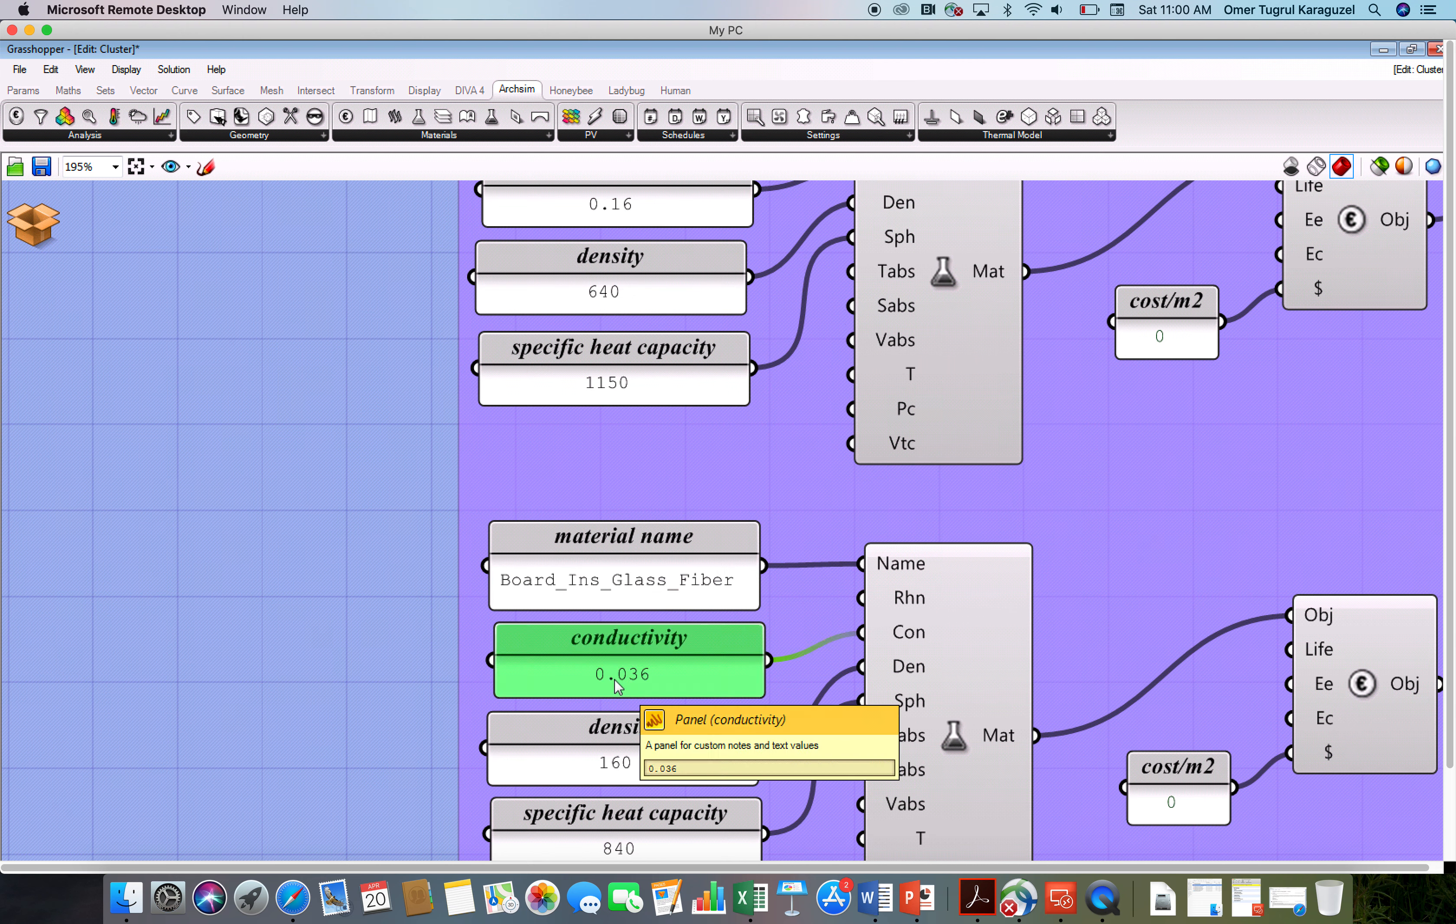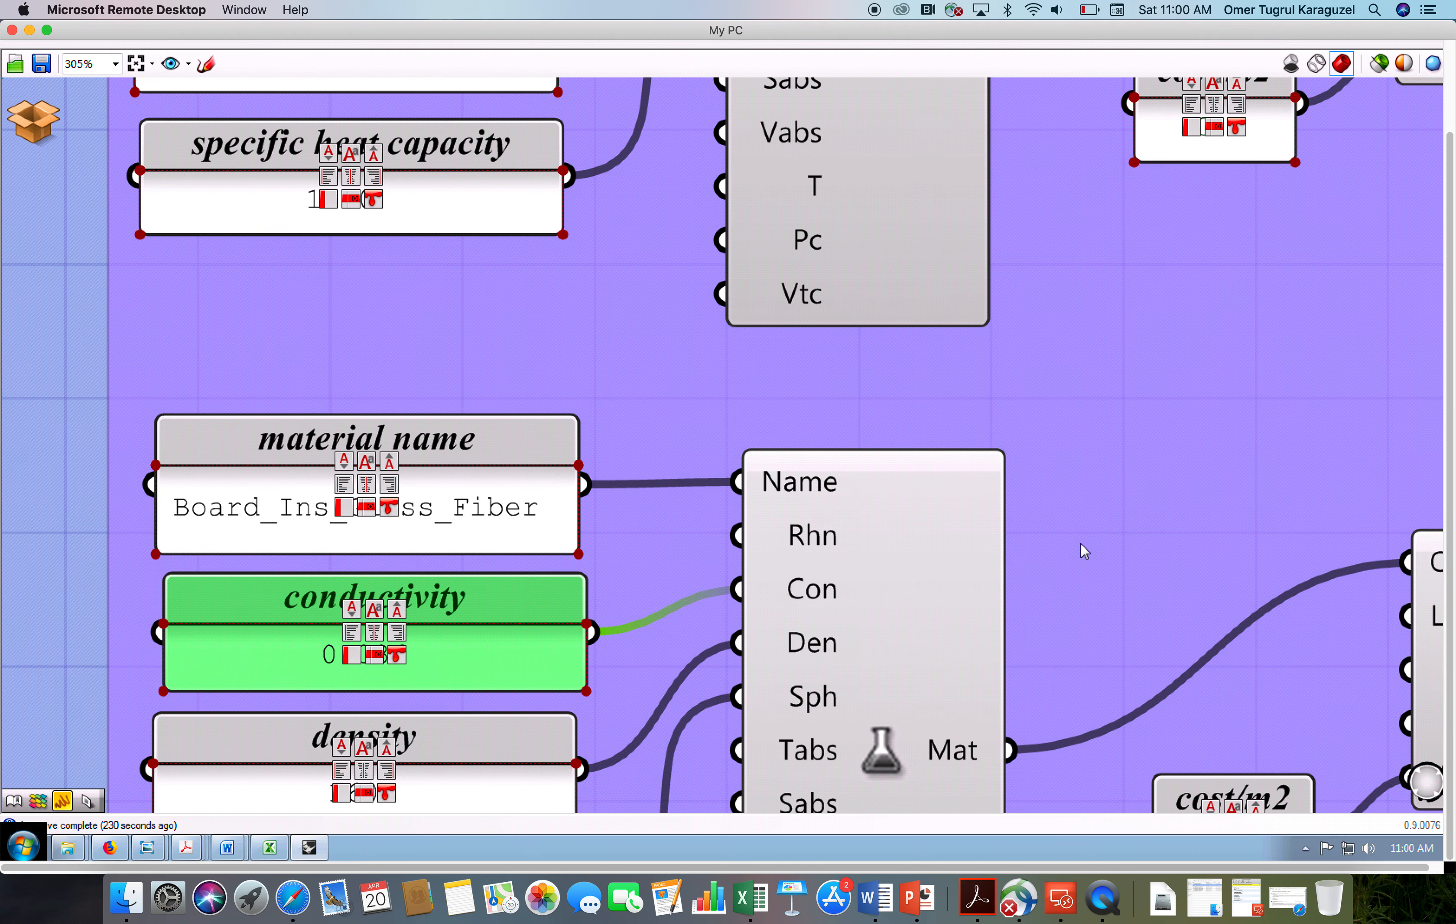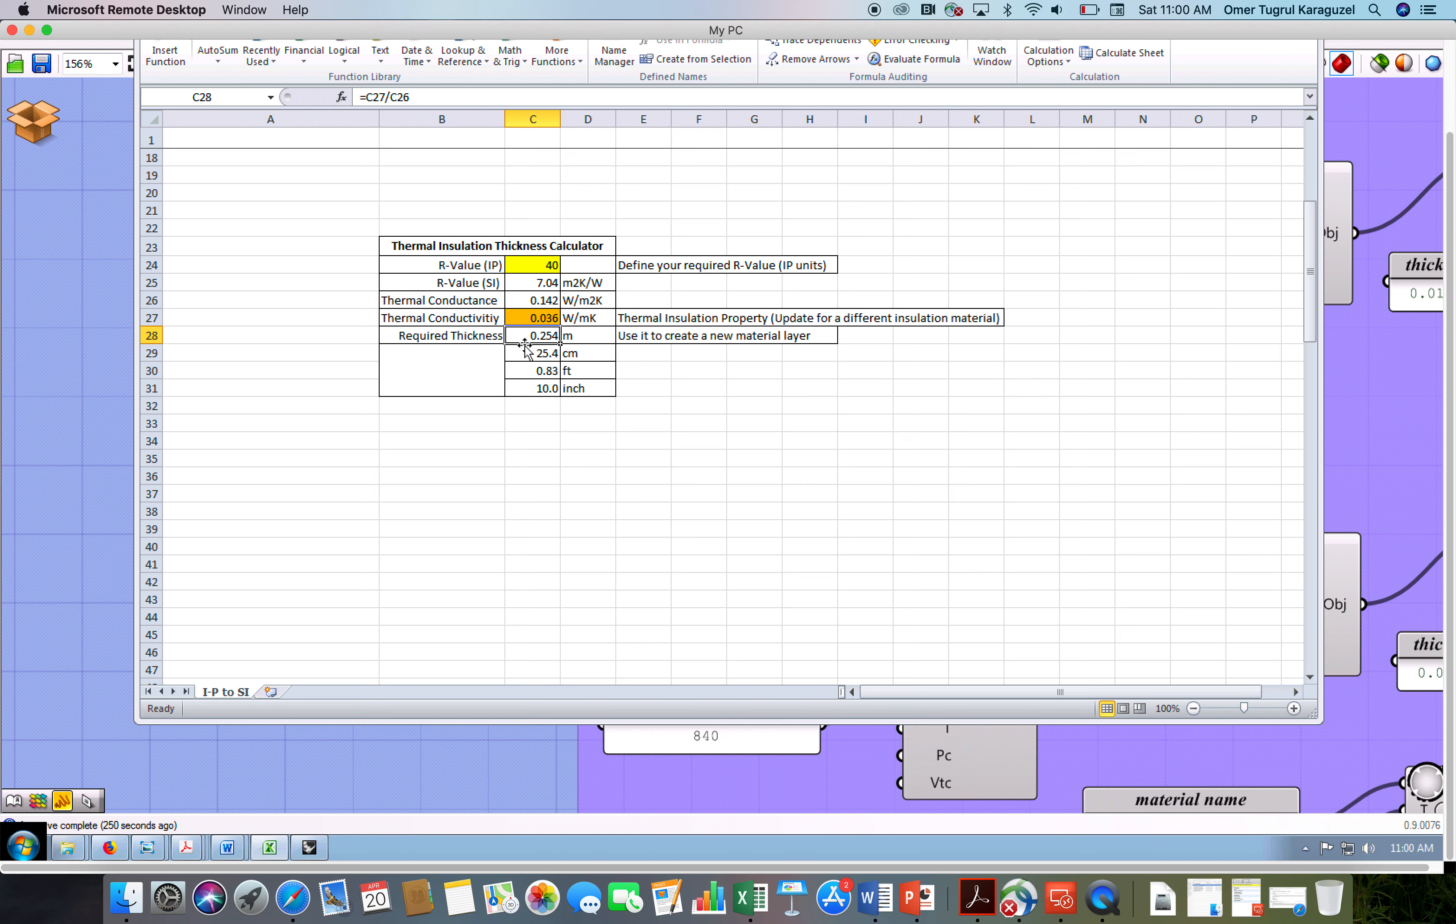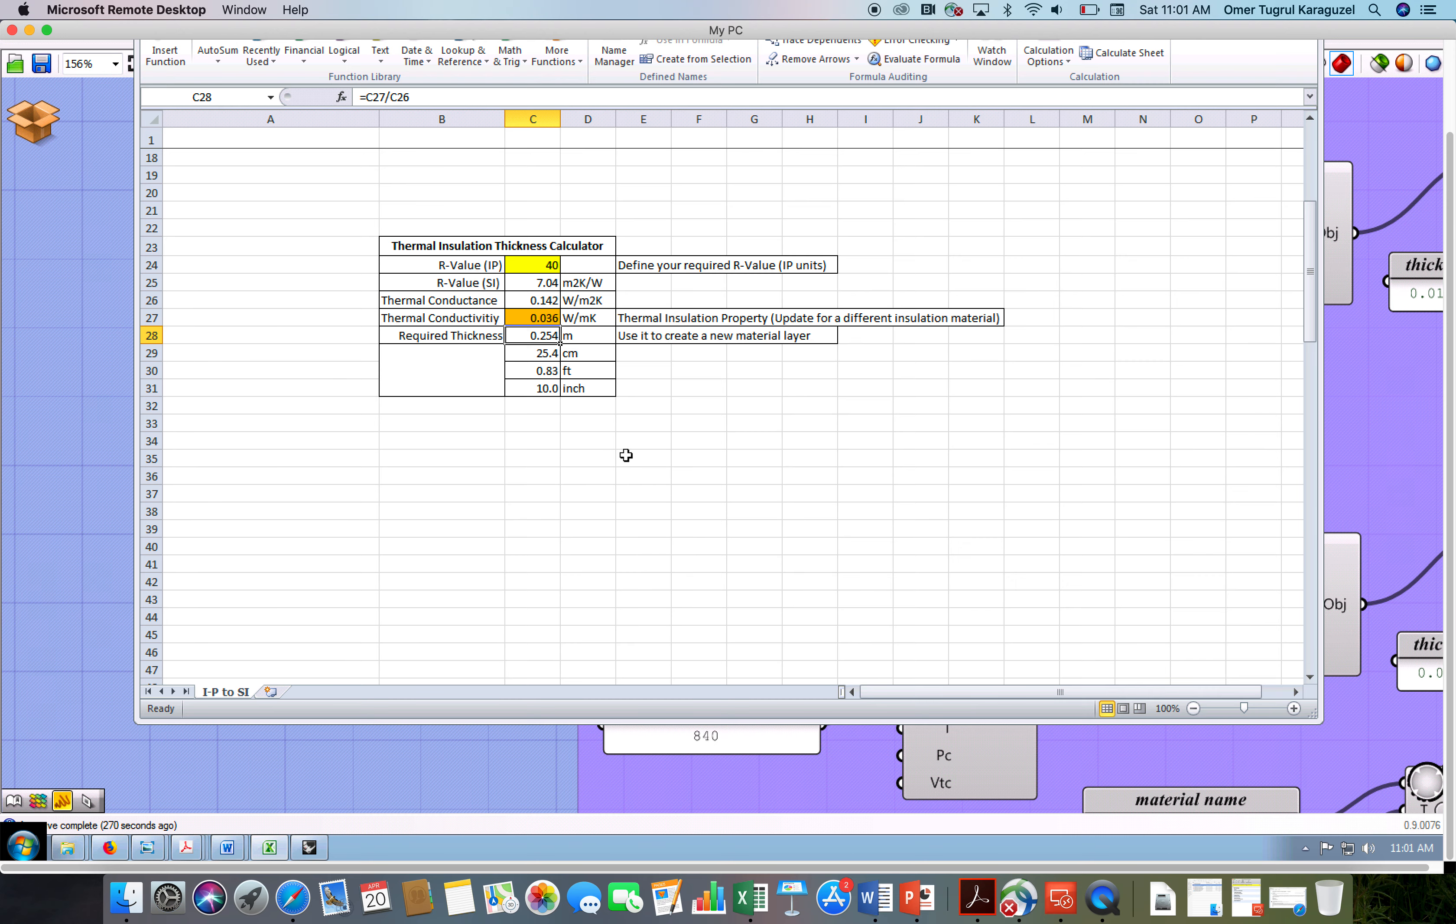And zoom in and have a look at your insulation thickness thermal conductivity. Right now it's 0.036. So keep this number and let's go back to our calculator. And I will update this insulation conductivity value. And then the outcome from this little Excel tool is the required thickness. This value. It's about 25 centimeters or 0.25 meters. I put some converters here. It's about 0.83 feet or about 10 inches of insulation thickness. So what to get now? This is already in the algorithm because we are updating an existing insulation material. But the information you need is this value, required thickness 0.254.